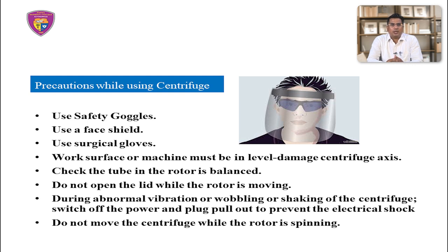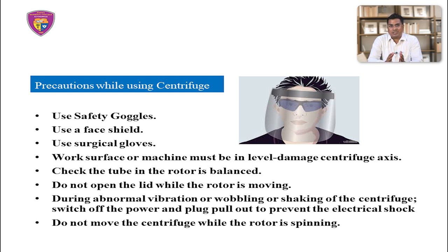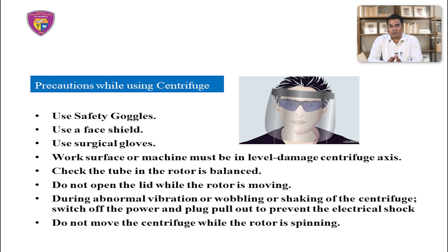Precautions for centrifuge use: use safety goggles to avoid aerosols present in the sample during centrifugation; use a face shield; use surgical gloves to avoid contamination. The work surface or machine must be level. Damaged centrifuge axes should be checked, and tubes in the rotor must be balanced. Do not open the lid while the rotor is moving to prevent any blast incident. During abnormal vibration or wobbling, switch off the power and pull the plug out to prevent electrical shock. Do not move the centrifuge while the rotor is spinning.